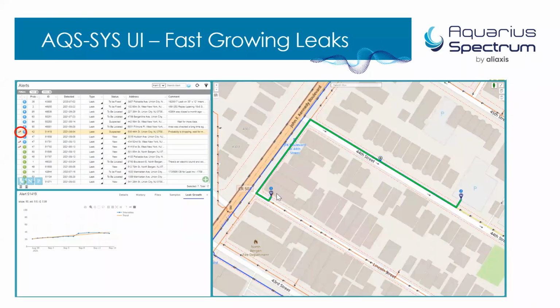There is the ability for the system to detect fast-growing leaks. With correlations through times and measurements of the intensity of the pattern matching, we can detect leaks that increase in their intensity through time, as is the case here. And this will be indicated in the analysis engine with a particular signal that calls the attention of the analyst to take care of those suspected fast-growing leaks in priority.